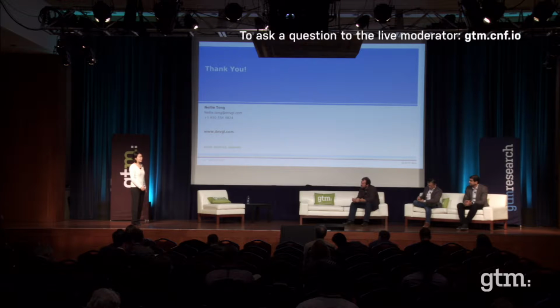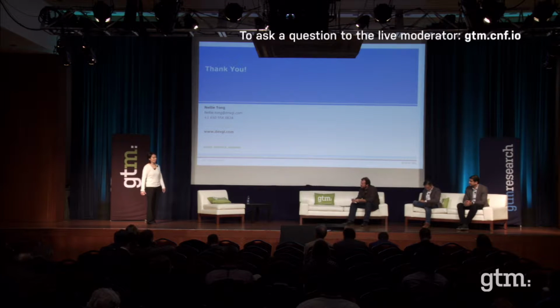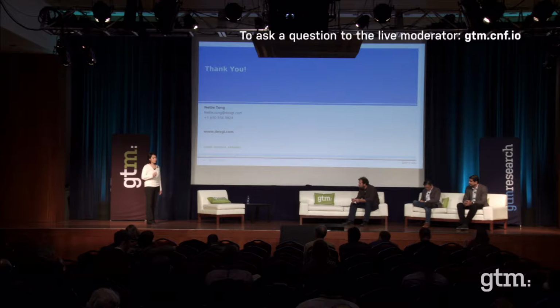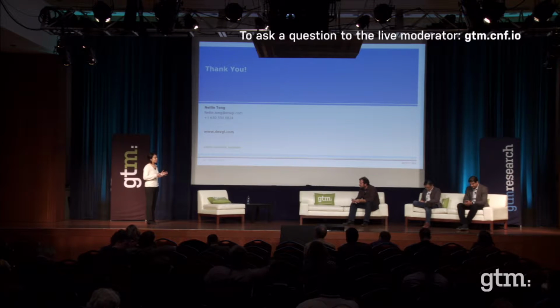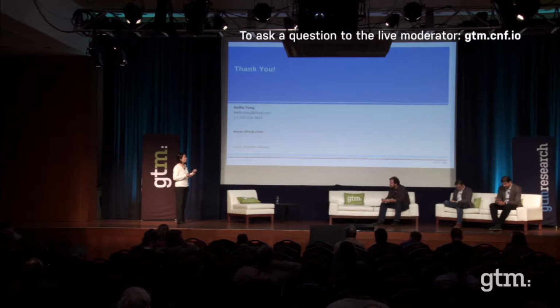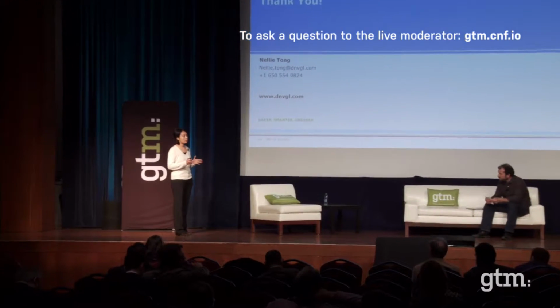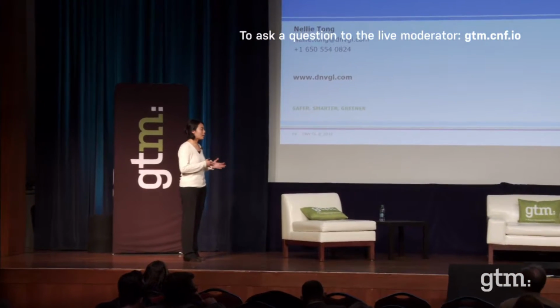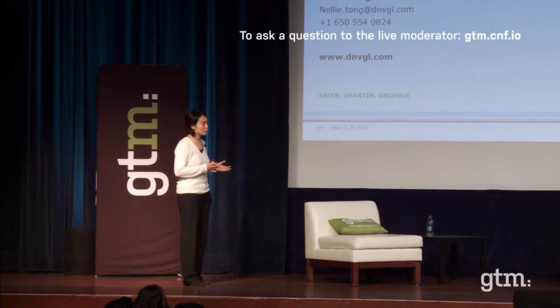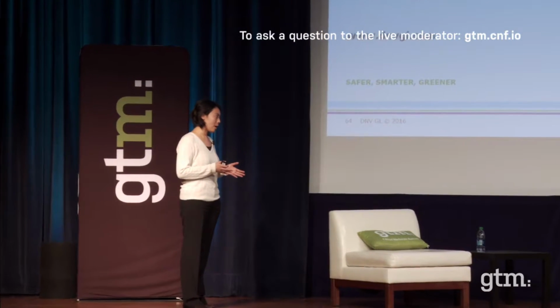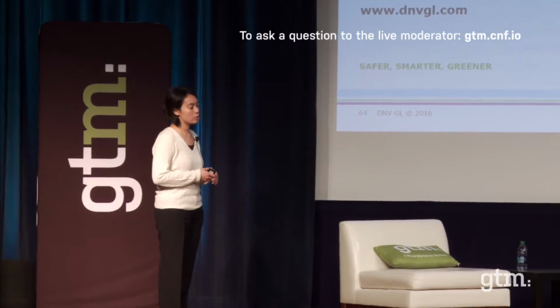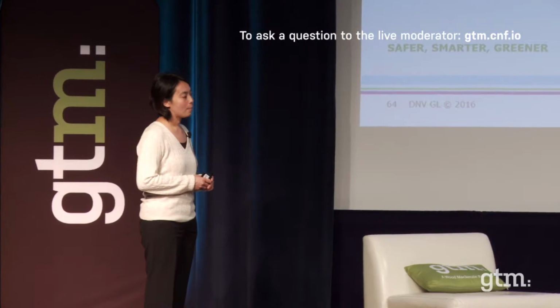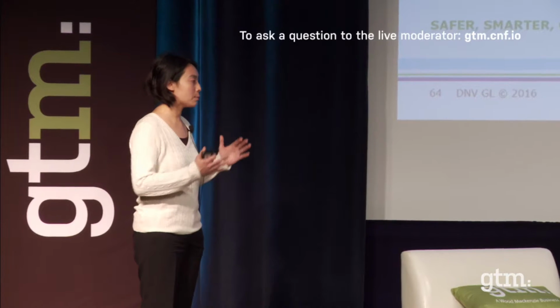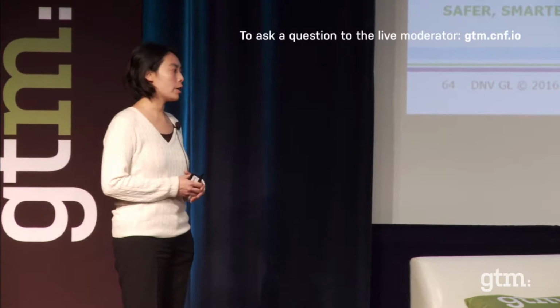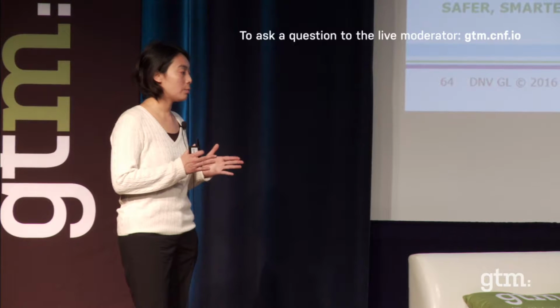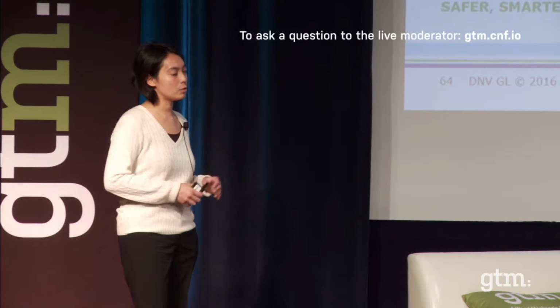It's actually pretty complicated to go through all the control theory and the algorithm for it. But first, we set aside 30 minutes of the storage, which in this case is a 2-hour storage, just for regulation. Then we calculate the demand charge reduction using the rest of the hour and a half, based on forecasts of load and generation, to optimize on a 15-minute basis how we can reduce the demand charge.